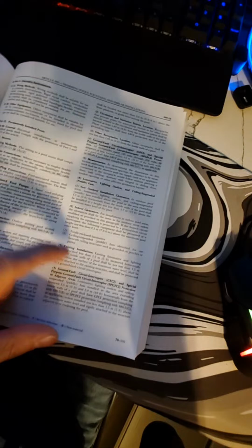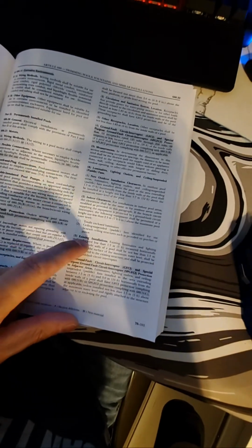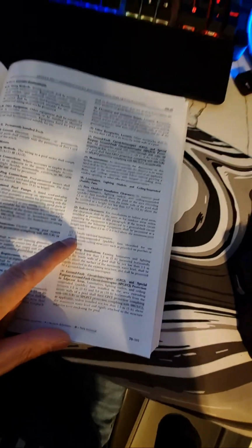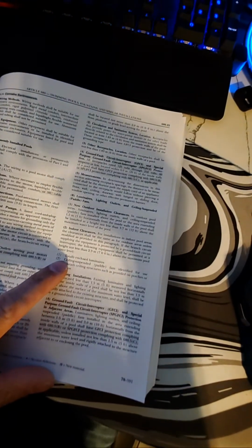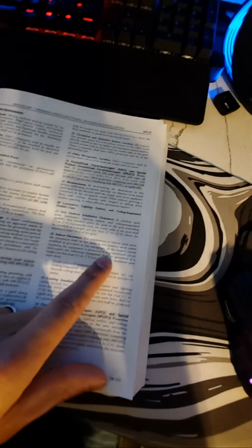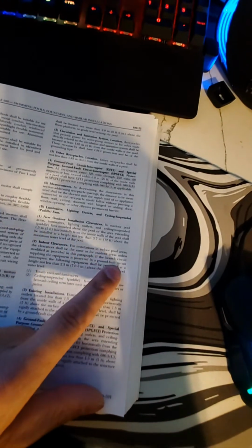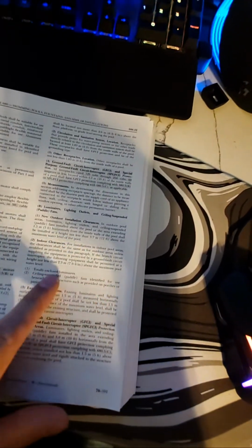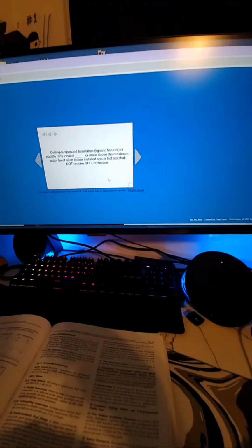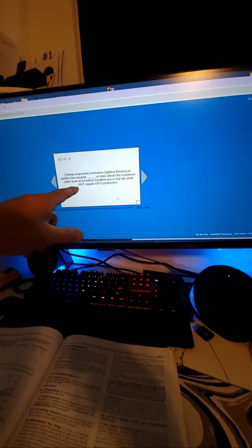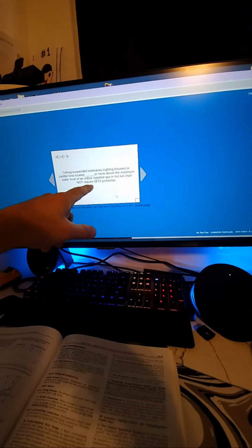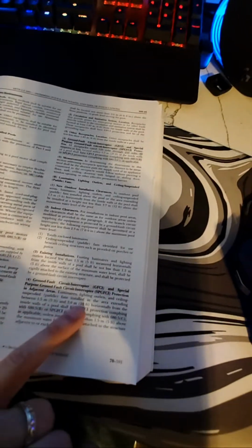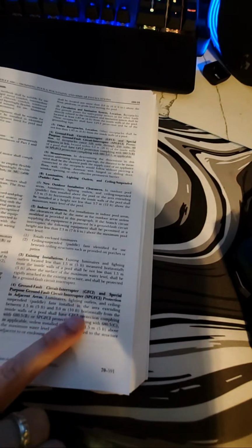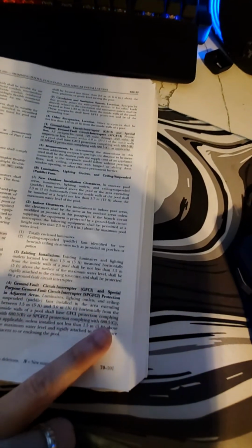and then you got existing installations, which if it's an existing installation, you get a little bit closer. But it looks like if the branch circuit supplying the equipment is protected by GFCI, the following equipment shall be permitted at a height not less than 7 foot 6. Okay, but it doesn't have a GFCI. Now what? Luminaire ceiling fans installed in the area extending 10 feet horizontally from the inside of the wall shall have GFCI protection.